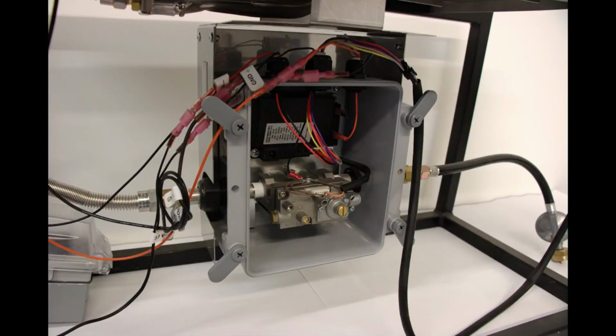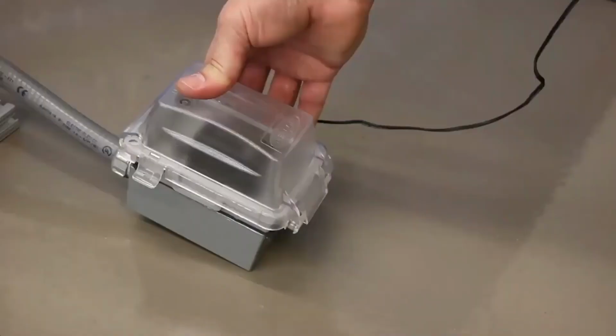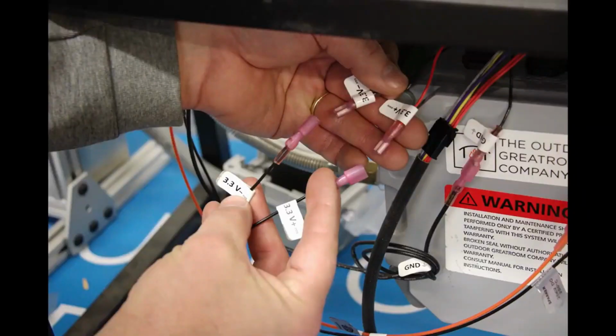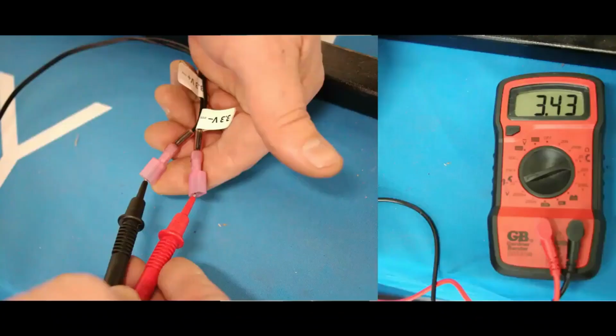If you can hear the beep, this indicates you should have sufficient power to the module. If you do not hear the beep, first check to make sure you have proper power supply. Make sure that your transformer is plugged into a covered electrical junction box. You can disconnect the leads from your transformer that lead to the valve and module and test for voltage. Place your multimeter in the DC setting and insert your probes into the transformer leads. You should read a fairly consistent 3.3 volts or higher.